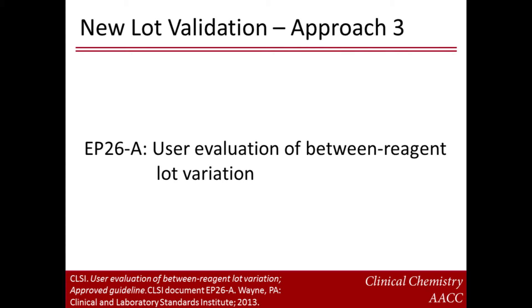Recognizing the importance of having a robust and standardized process for reagent lot validation, the Clinical and Laboratory Standards Institute, or CLSI, also released a guidance document in late 2013 for the user evaluation of reagent lot-to-lot variation. The document provides a simple, practical, and statistically sound protocol to evaluate the consistency of patient sample results when a new analytical reagent lot is to replace a reagent lot currently in use. It provides guidance on establishing acceptable performance criteria, choosing a desired statistical power to detect differences, determining the number of samples to be tested and acceptable sample types, as well as designing a process for evaluation of lot-to-lot differences.